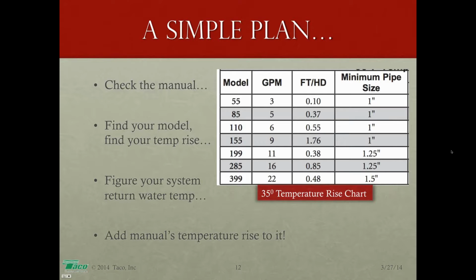Again, this is why we want the big fat header. What you just explained there, Dan, is why hydraulic isolation in mod cons is so critically important. Absolutely critically important. We could size that header to 1 inch, and I think a lot of what you say would probably happen in the boiler, making it short cycle. The bigger we make that header, the less likely that is to happen, to the point that if we go to a hydraulic separator or even a buffer tank, those problems virtually disappear. So I absolutely understand what you're saying, I hear what you're saying, but there's a reason why we try to do it the other way, so that doesn't happen.